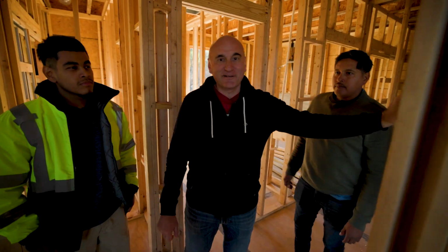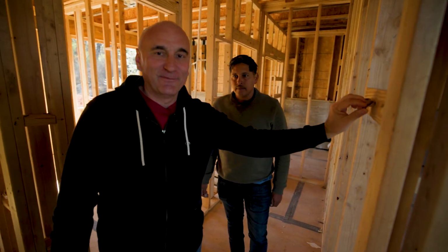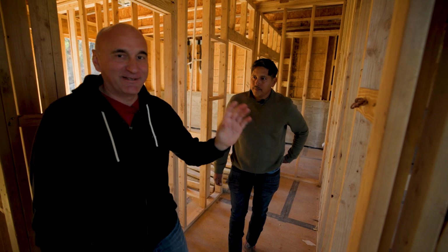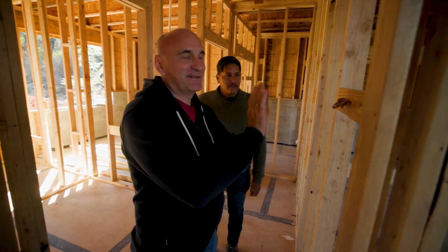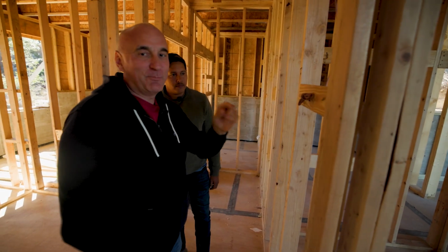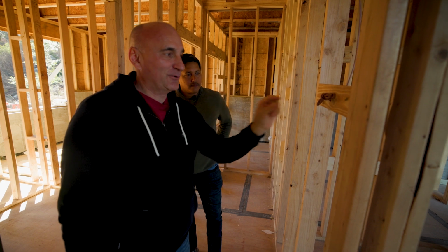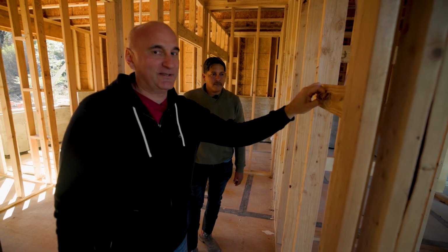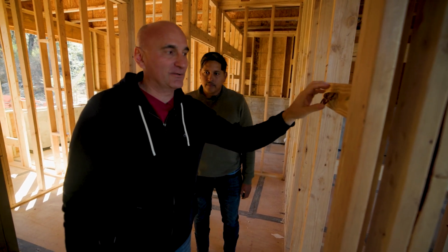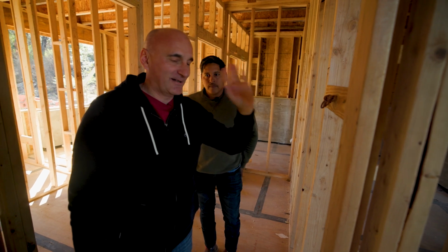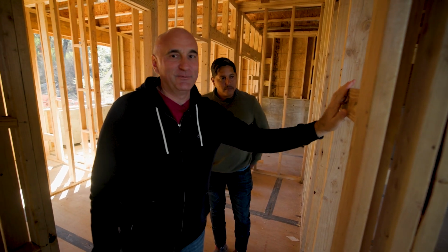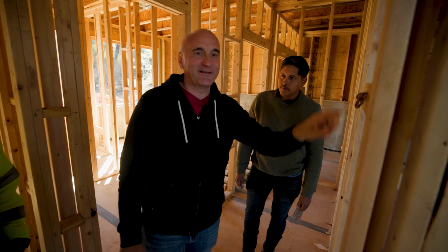Just one tip, guys. You see this wire? A lot of times when your drywall guys come to install drywall, they cover this wire. Pay attention to this wire, because this is the thermostat wire. If you do not pay attention and the drywall guys cover it, it will be a big problem. You have to cut the drywall, open it and find it.